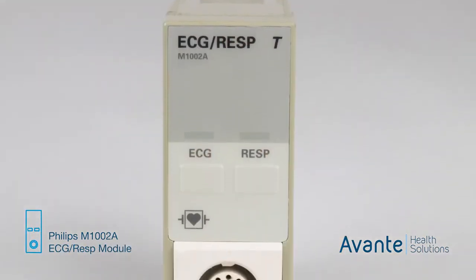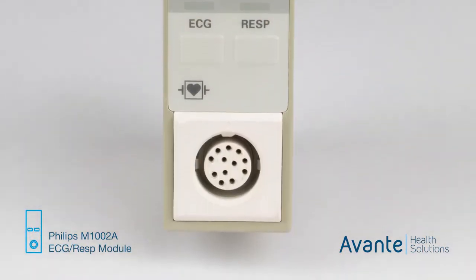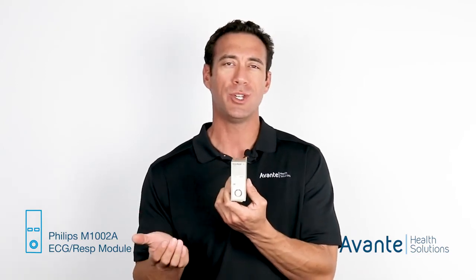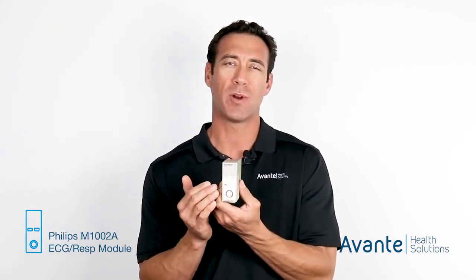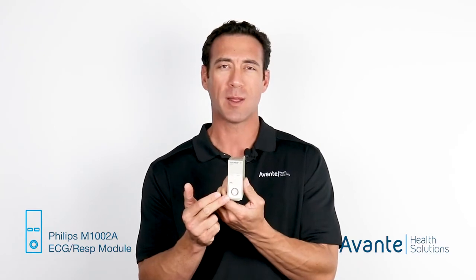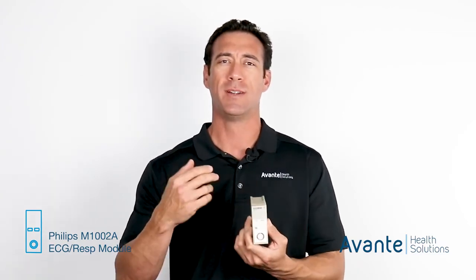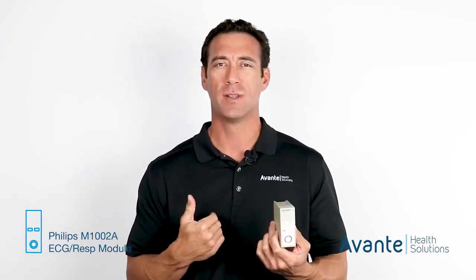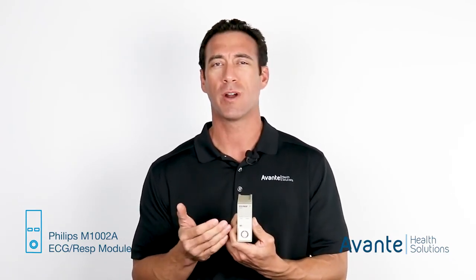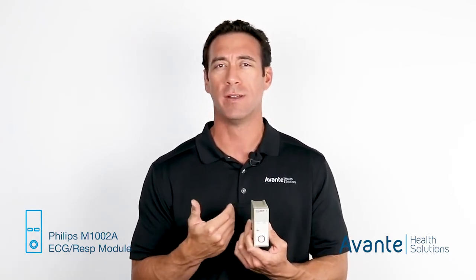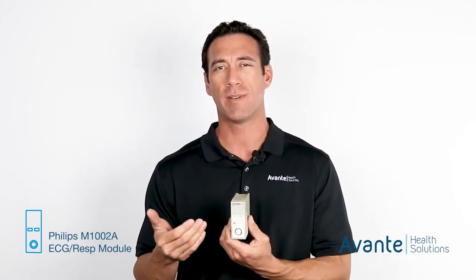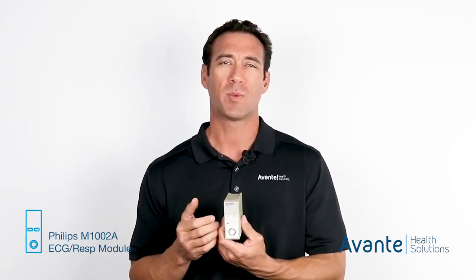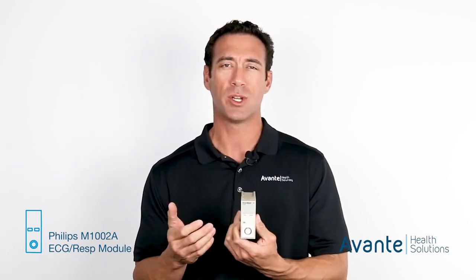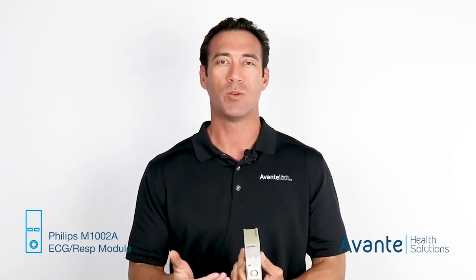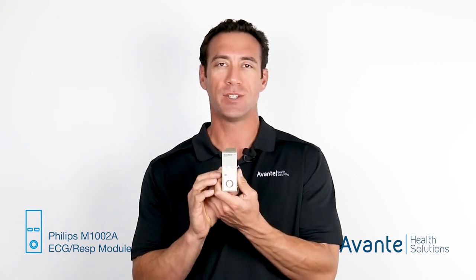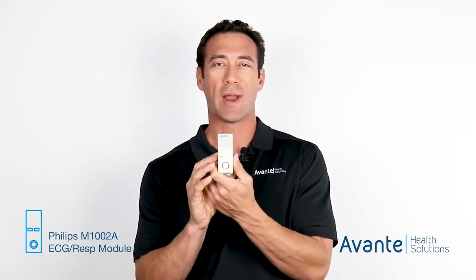So here I'm holding the Philips M1002A. This is going to measure ECG / respiration. So you're going to have the patient cables attached to the front of the module, right to the patient via electrodes. It's going to measure that ECG or electrocardiogram, which is going to be the electrical current of the heart. And at the same time, we'll also give a measurement or a number for respiration cycles and rates. So as a patient breathes in and then breathes out, it will be able to show that on the monitor. This is your ECG / resp module.